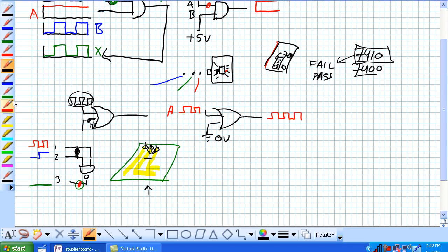The other thing is, remember, these are on the other side. You know, you could be looking at a printed circuit board. Yep, that's hooked up there. That's hooked up there. I don't know what the problem is. Well, check it out. Spin it over on the other side. Here's our conductive paths. And there's the quarter that you lost the other day in the access box banging around, and it has landed stuck onto there, and it's shorting out these two connections there. So be aware of that. And the quarter story is true, guys.